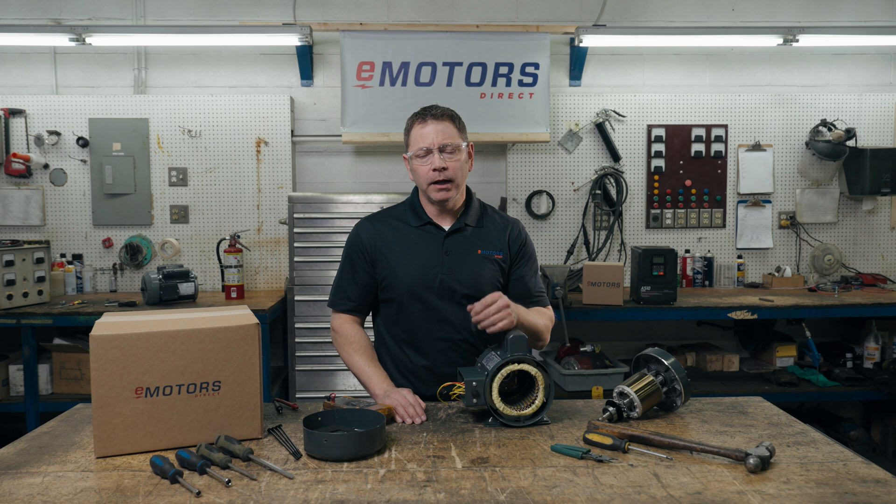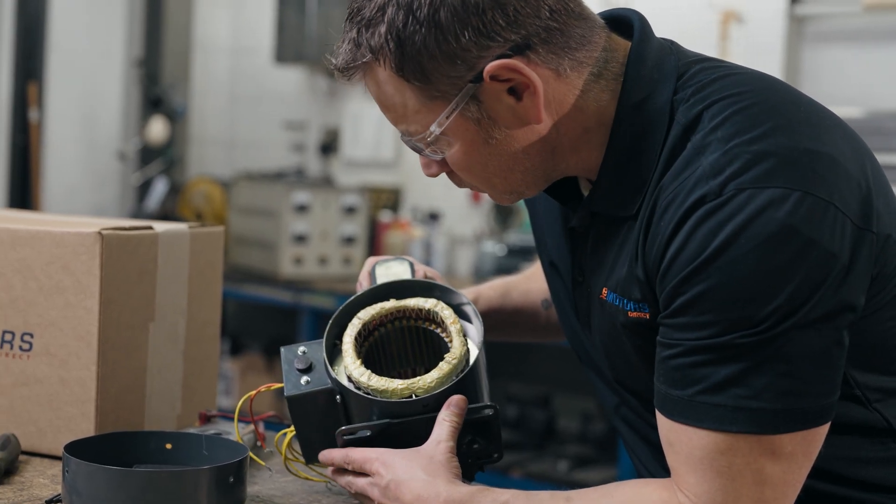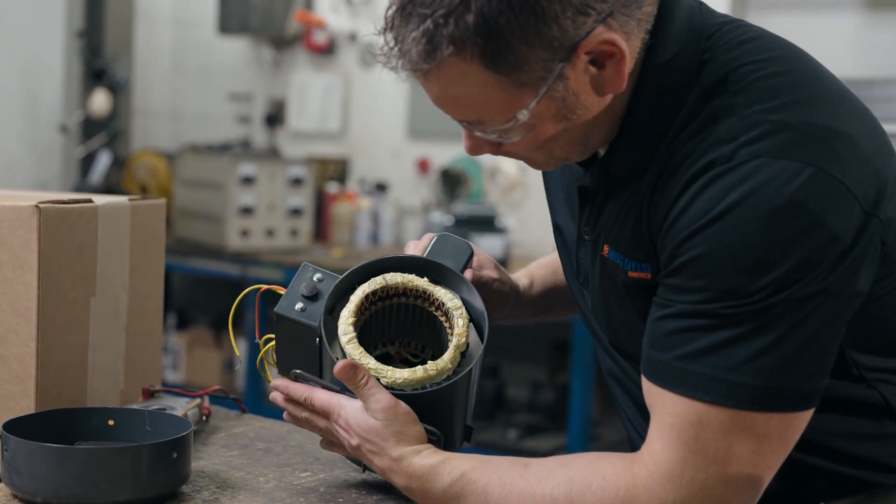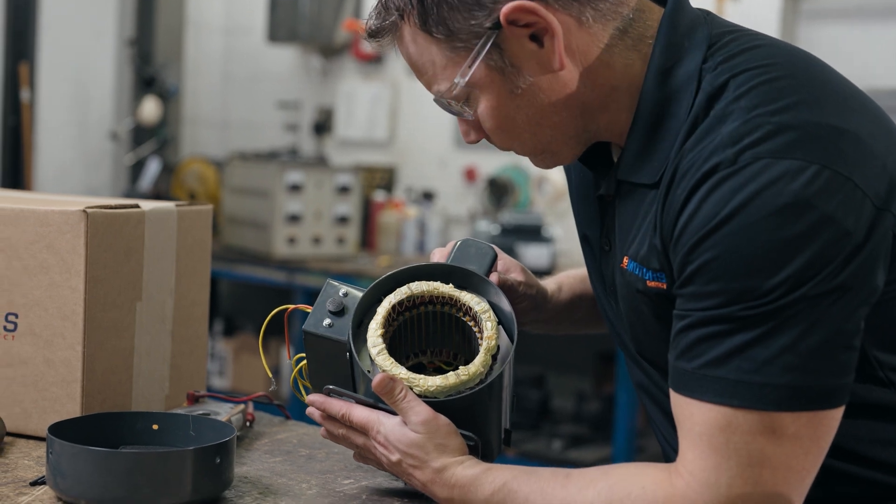Next, you'll test your capacitors — check out this video for a step-by-step guide. Then remove the end bell and do a visual inspection of the motor windings. You're looking for burns, melting, or breaks in the motor windings. If you do see burns, your motor's likely been overloaded and will need to be repaired or replaced.